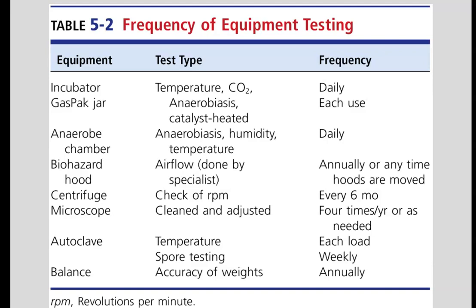Autoclaves: the temperature should be checked regularly, and spore testing to make sure the autoclave is actually autoclaving effectively should be done on a weekly and/or monthly basis. Any kind of balance or scale that you have should be checked annually to make sure it is working properly.